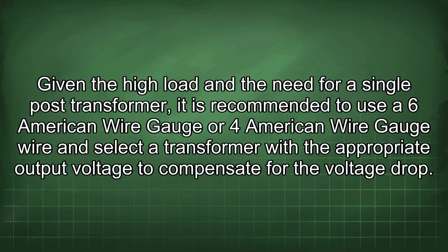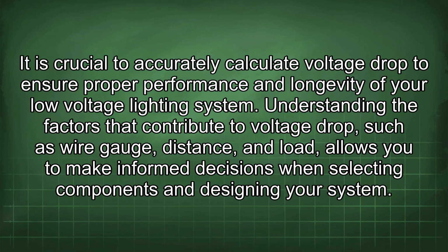Given the high load and the need for a single post transformer, it is recommended to use a 6 American wire gauge or 4 American wire gauge wire and select a transformer with the appropriate output voltage to compensate for the voltage drop. It is crucial to accurately calculate voltage drop to ensure proper performance and longevity of your low voltage lighting system. Understanding the factors that contribute to voltage drop, such as wire gauge, distance, and load, allows you to make informed decisions when selecting components and designing your system.